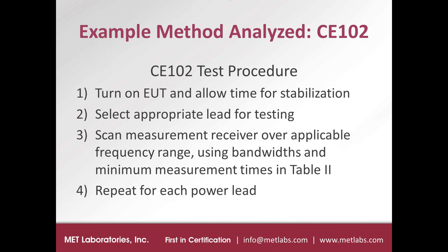And then you're going to use the test equipment and the test software to scan the measurement receiver over the applicable frequency range. You have to make sure that your software is set up to control the spectrum analyzer to use the required bandwidth settings and the minimum step times and measurement times indicated in Table 2 of MIL Standard 461. And that procedure is going to be repeated for each power lead.